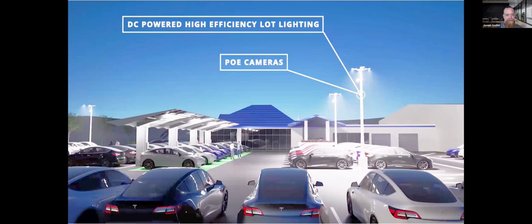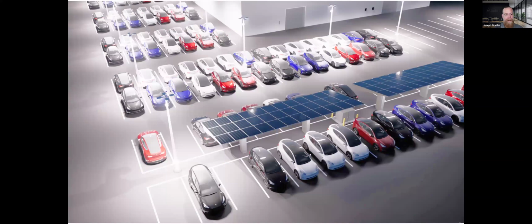This is the final phase of our renovations, and we're planning a dedicated outdoor microgrid system to power all of the dealership lot lighting and security cameras. Each security pole includes either 3 or 4 high efficiency LED fixtures and a network-connected pan-tilt-zoom camera, routed through the PoE network for monitoring. The lighting system will be powered by 2 additional shade structures in the back. These are split apart but total up to 24 kilowatts, feeding a microgrid housed in an outdoor weatherproof enclosure.